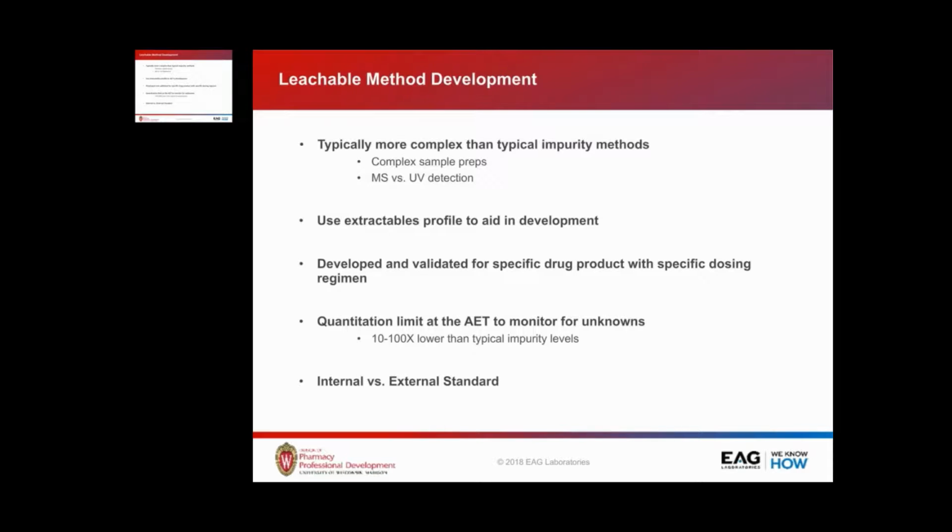And then you have to make a choice between an internal and external standard. There's two different techniques here where you're quantitating against an external standard. But then also internal standards can be very useful, especially for very complex systems or very complex sample preparations, in that having an internal standard helps to correct for any potential biases that you can unfortunately run into with some complex sample preparations, especially derivatization. If you have to do that, internal standards almost are a requirement at that point.